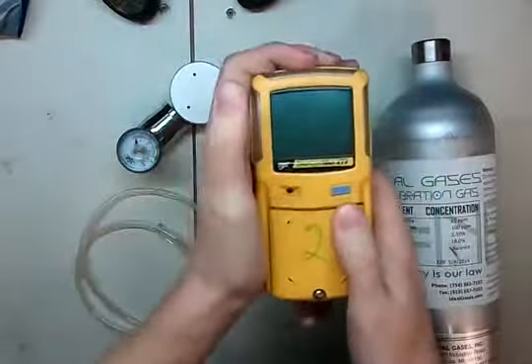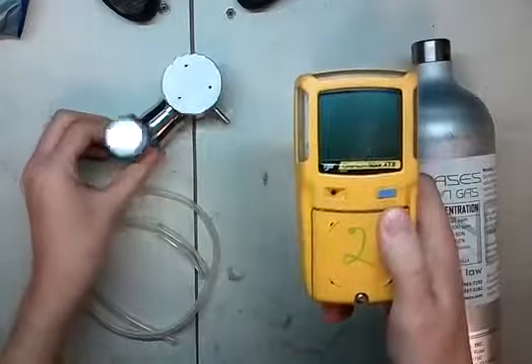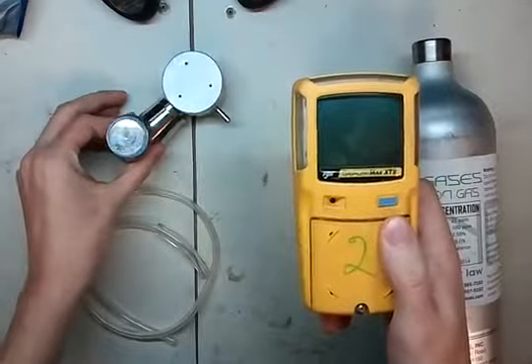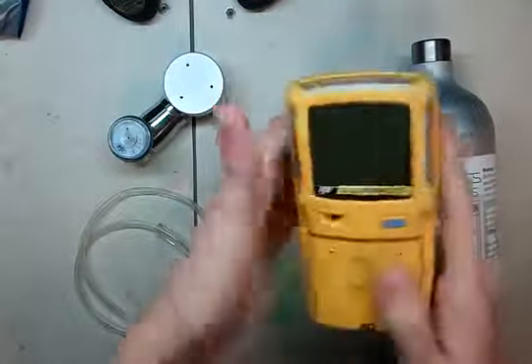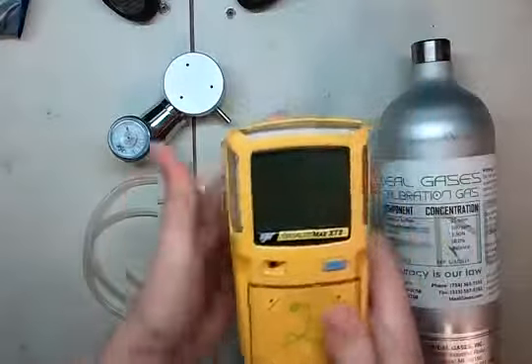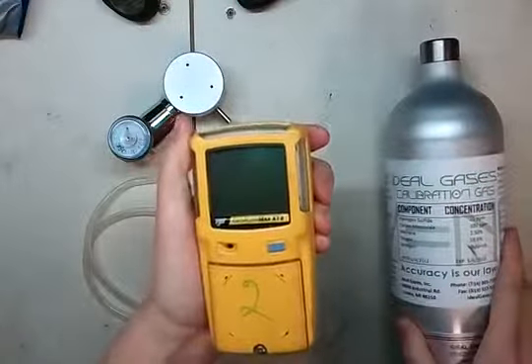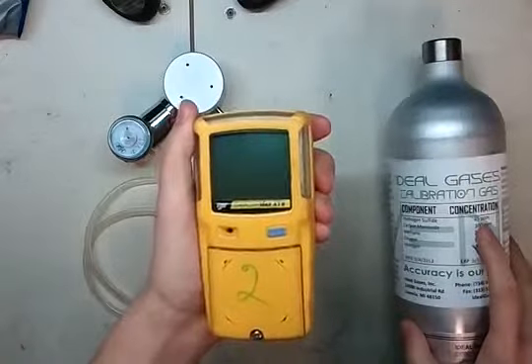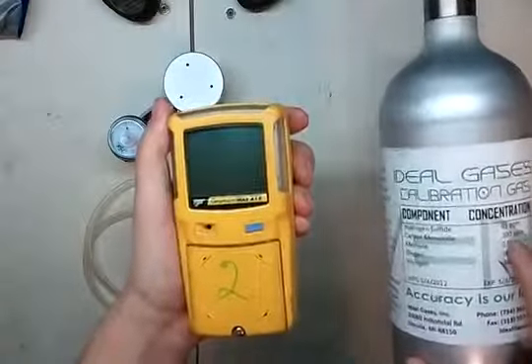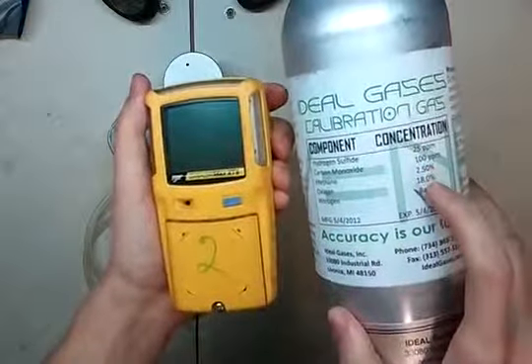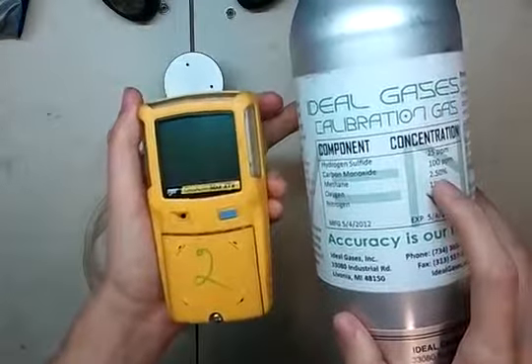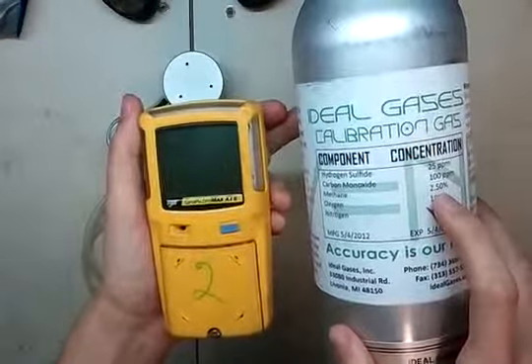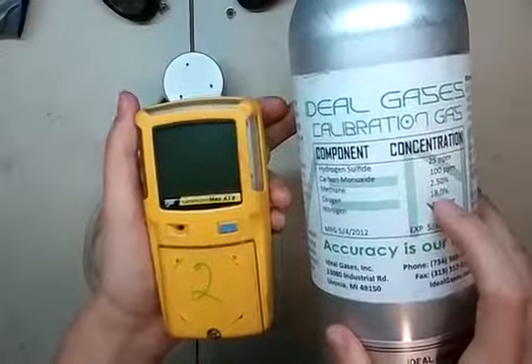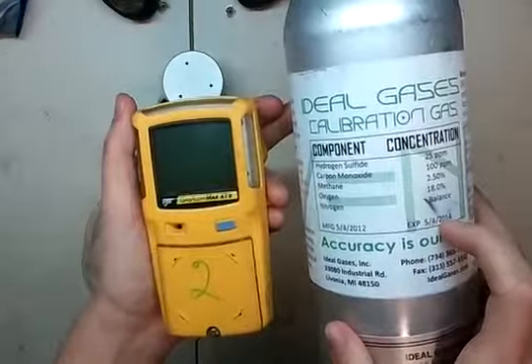Okay, what you're going to need is your gas monitor, your regulator here. Today we're going to use a demand flow regulator because this unit has a pump in there, some tubing, and a cylinder of calibration gas. The cal gas values you need are 25 parts per million H2S, 100 parts per million carbon monoxide, 2.5% methane by volume, which equals out to being 50% LEL methane, and 18% oxygen with a nitrogen balance.